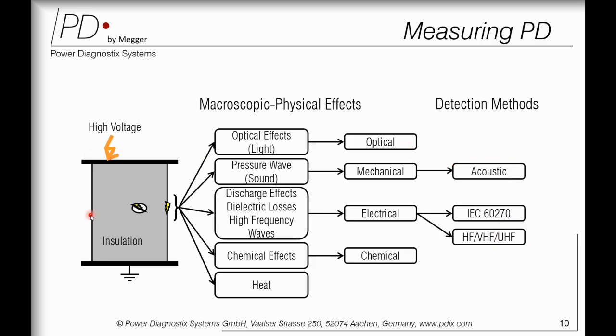So I will take an example on this because there is a lot of confusion in the market. Somebody says we do electrical method, somebody says we do UHF measurement, somebody says we do acoustic measurement, somebody says we do HFCT. Which is the right method? I would like to explain the measurement techniques with this small drawing. On the left hand side, you can see my asset under high voltage, and due to some impurities, you can see it is creating some partial discharge. And this partial discharge, PD, emits some energy.